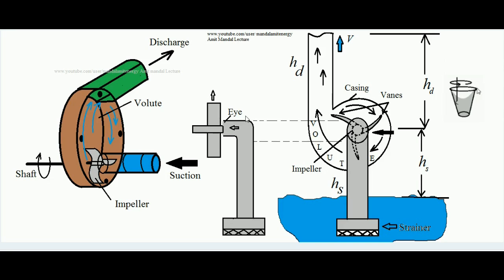Water automatically lifts up and reaches the impeller because the impeller vanes are throwing water due to centrifugal force toward the inner peripheral surface of the casing. High pressure water is collected there and exits from the system through a corresponding exit. Continuously, as water is going out it is creating a void inside, and due to that void a vacuum is created. Due to that vacuum more water is pulled through the suction pipe to the impeller — it is a steady process. The space inside the casing other than the region where the impeller rotates is called the volute.